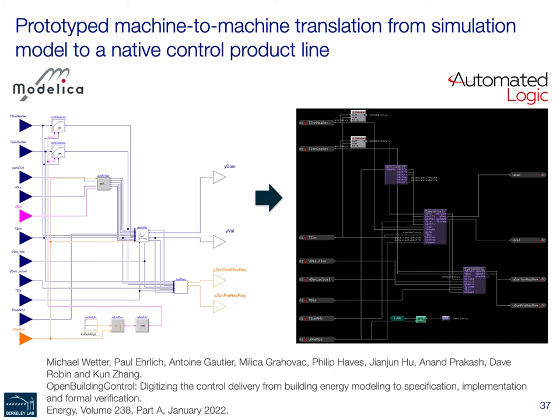And what you see here is now the one-to-one translation that has been done via machine-to-machine translation. On the left, you see the Modelica implementation, or the control description language, which is a subset of Modelica. You see, for example, on the top left, the two PI controller, and below that, the active airflow set point control sequence.